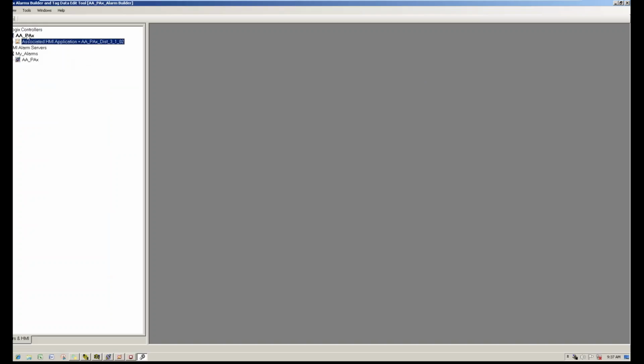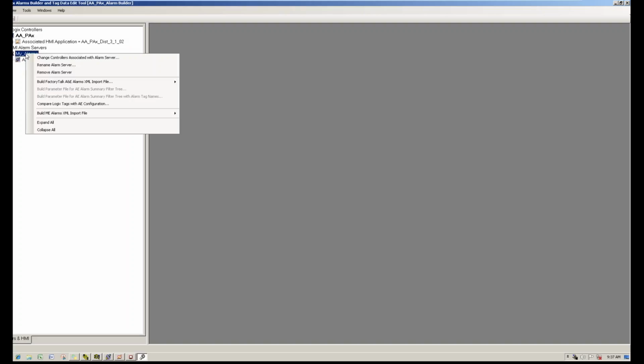Just because of the time that we've got here, I've already done that for you. So yeah, it really does only take 2 or 3 minutes. It takes the Logix 5000 file, converts it to an XML format, and brings it into this Alarm Builder tool. Once I've done those two configuration things, I simply come down here to where I've got my alarm server configured, and I build my FactoryTalk alarm import file.